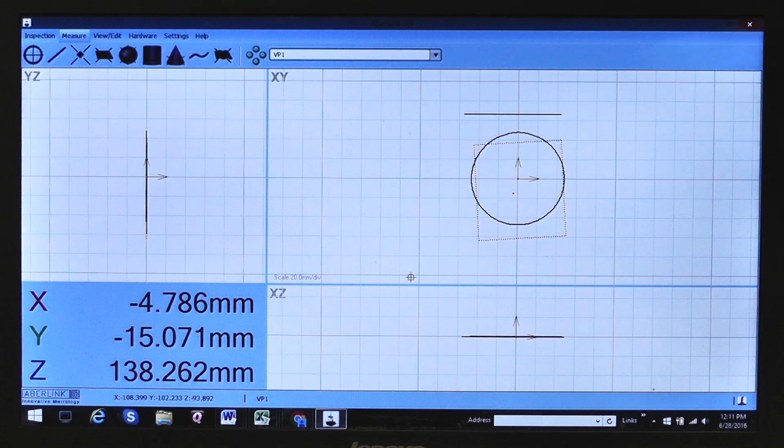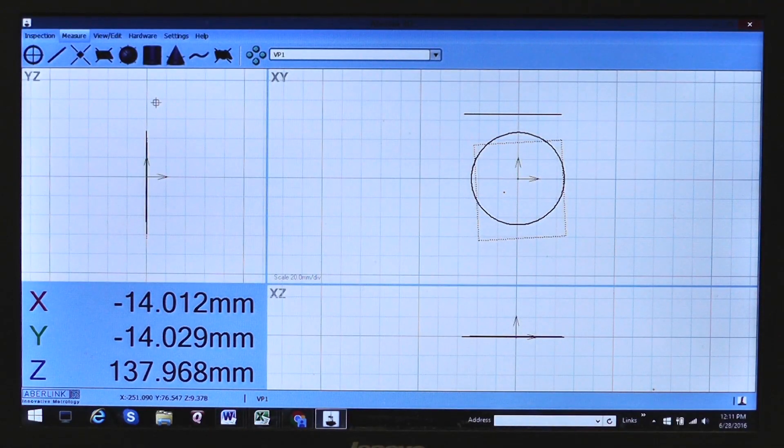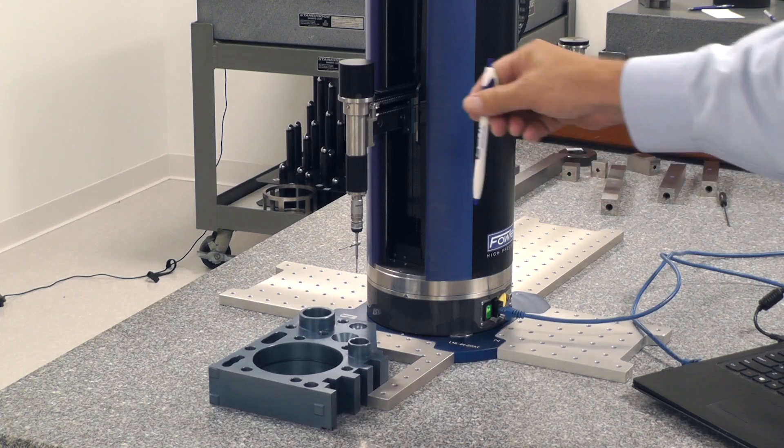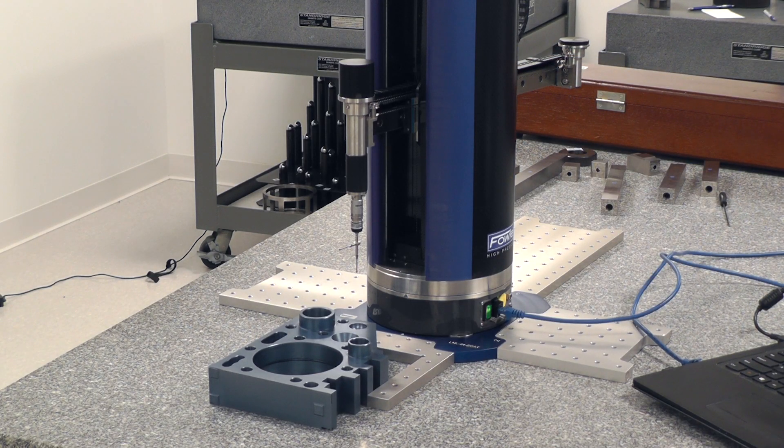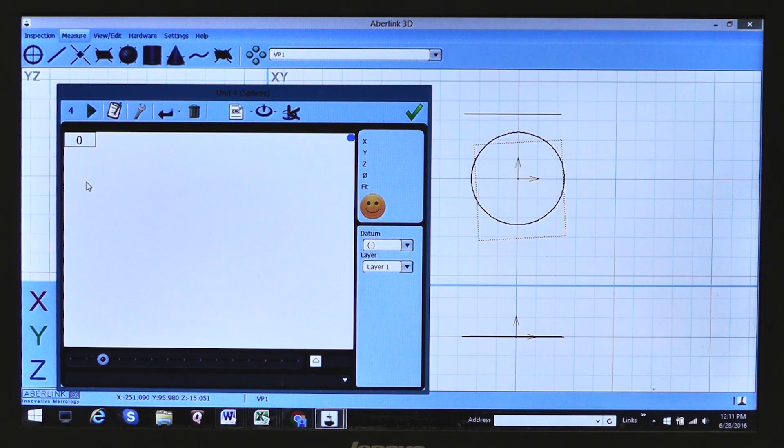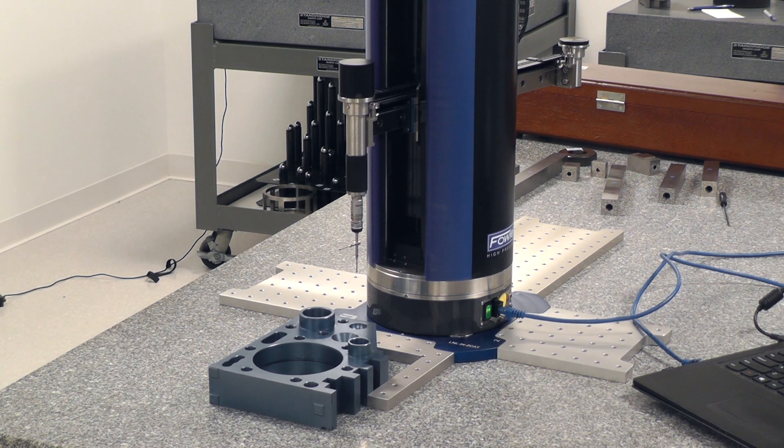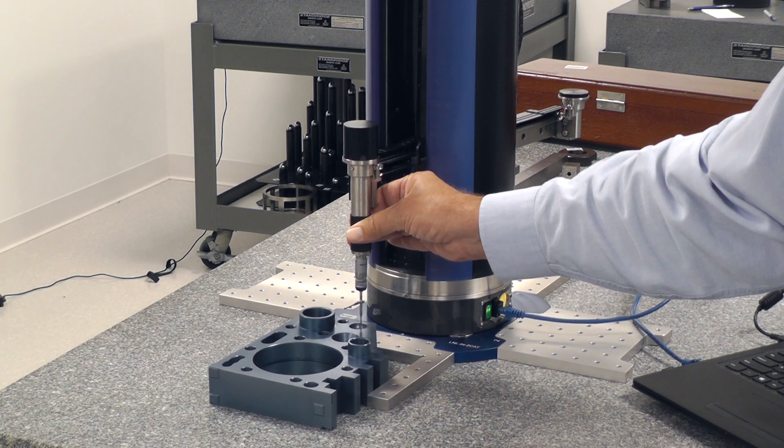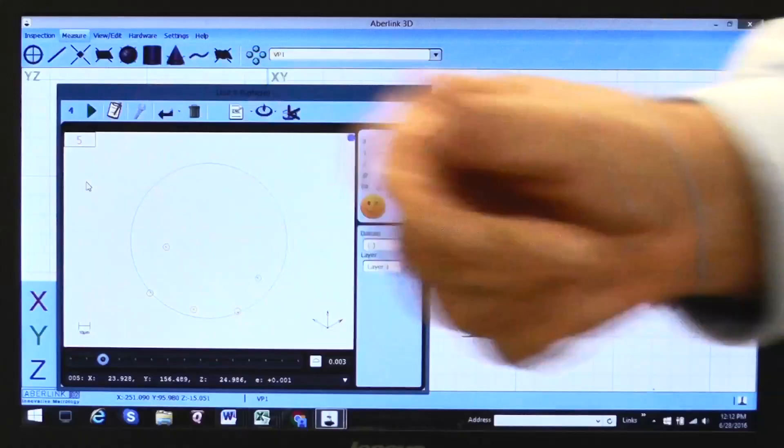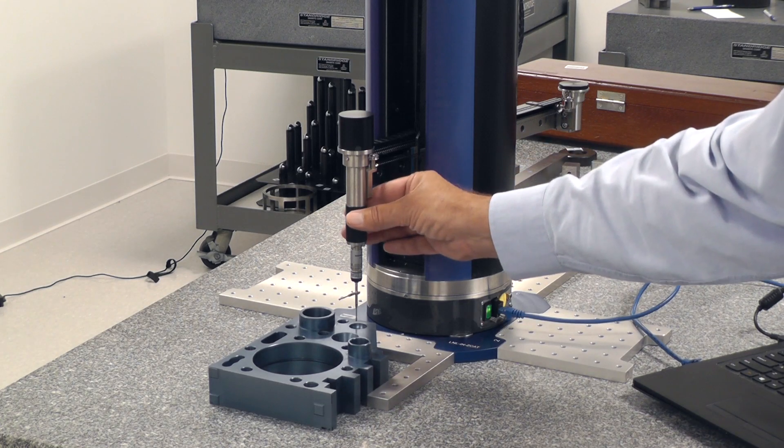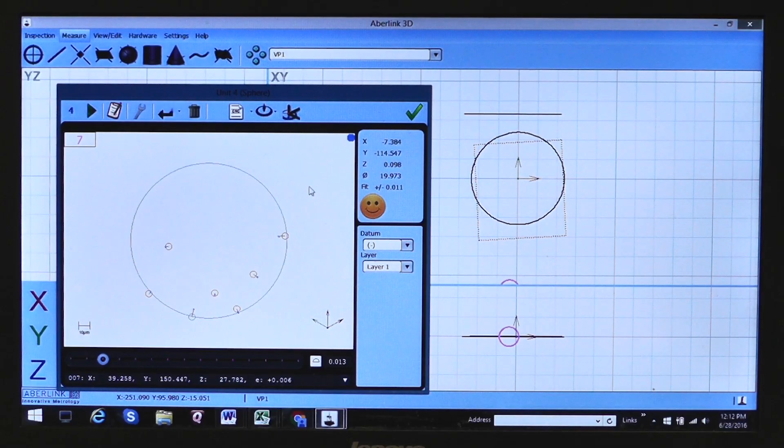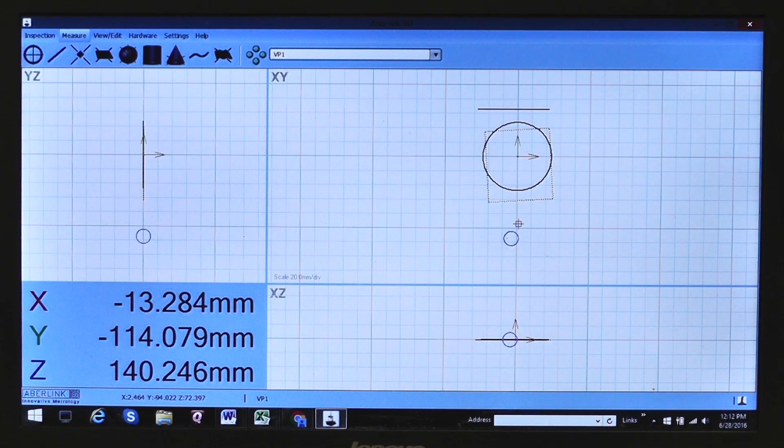Let's measure a sphere. So I'm going to click on the sphere icon. There is a small sphere in this demo piece. You'll also notice I'm using the vertical probe right now. The operator does have to tell the software which probe we're using, which stylus we're using, whether it's the vertical or the horizontal. Because this is a standard Renishaw TP20 touch probe, it sends the same signal. So we have to tell it. In this case, I'm using the vertical probe. I'll come down here and start taking a few points. As soon as I have enough points, it will create a sphere on the screen. I'll take a couple more, raise it up, and then confirm it with the check mark. So it's created that sphere here.